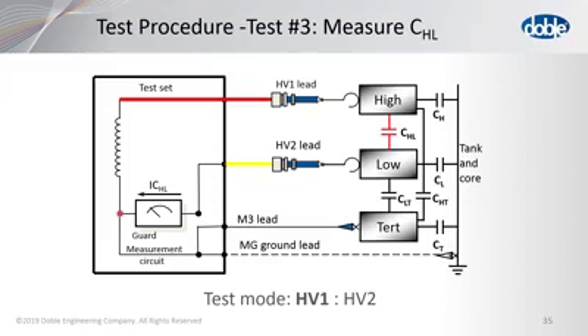Let's say that you can run the first test at 10 kV, then you'd run a 2 kV test, and then you look to see if there's what we call a tip-up. Usually those two tests should get about the same power factor. A tip-up might indicate a problem.